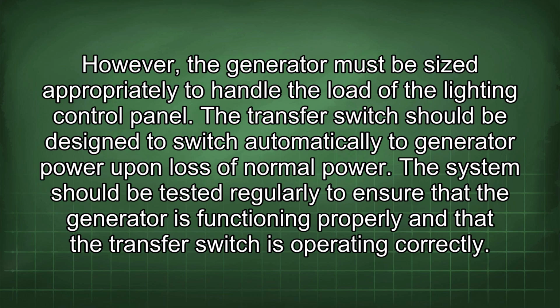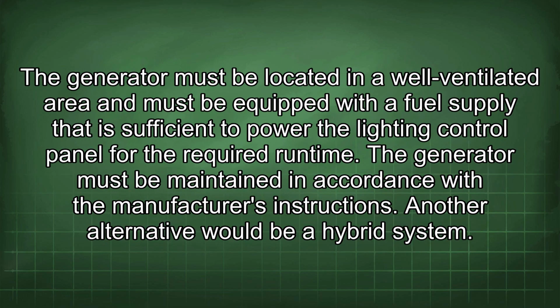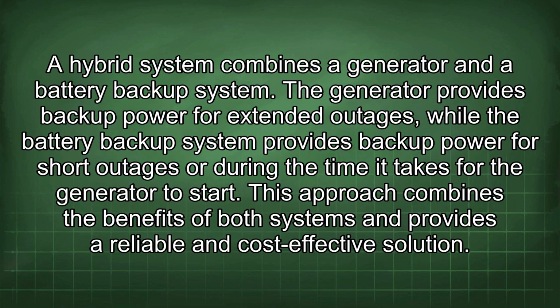The system should be tested regularly to ensure that the generator is functioning properly and that the transfer switch is operating correctly. The generator must be located in a well-ventilated area and must be equipped with a fuel supply that is sufficient to power the lighting control panel for the required runtime. The generator must be maintained in accordance with the manufacturer's instructions. Another alternative would be a hybrid system. A hybrid system combines a generator and a battery backup system.